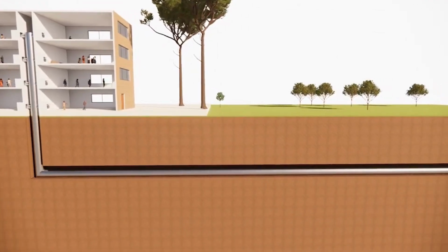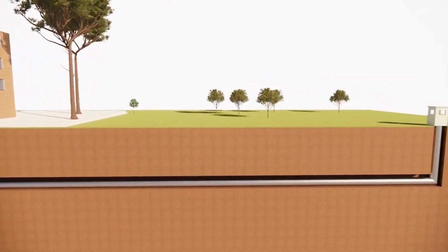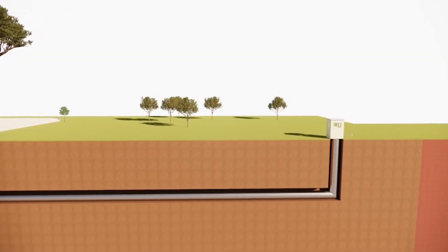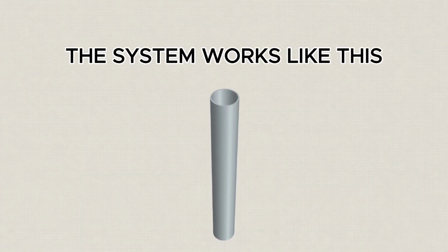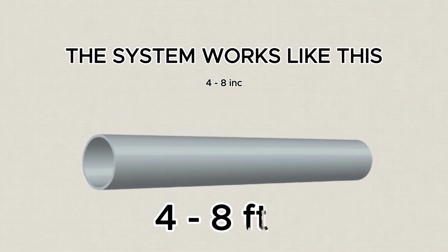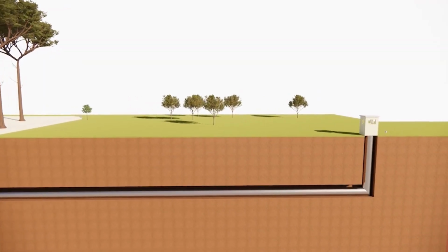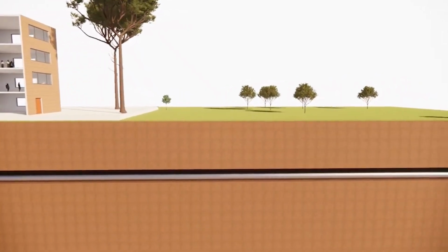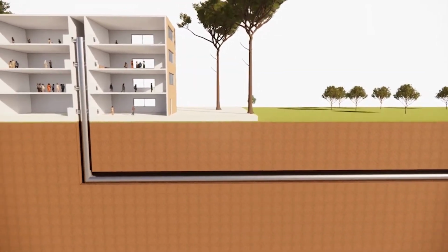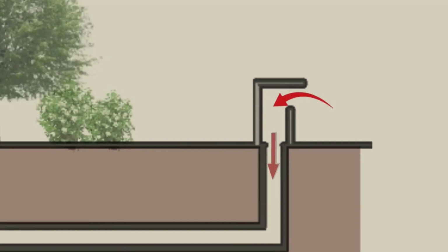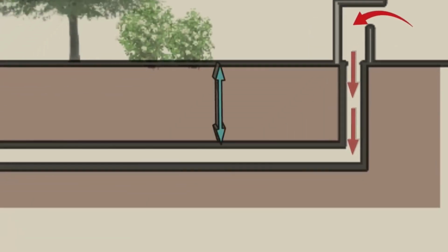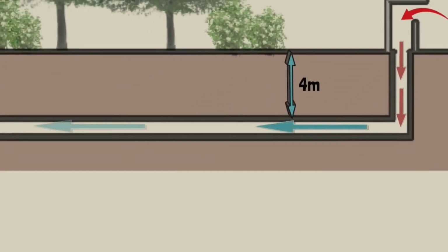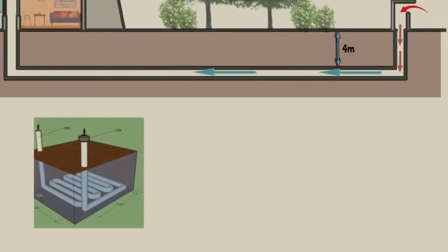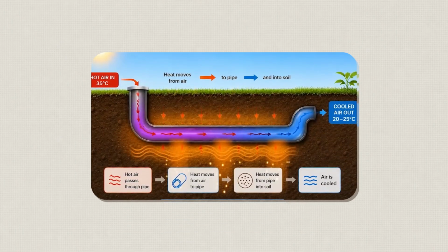An earth tube, also called an earth air heat exchanger, or EAHE, exploits that difference directly. The system works like this. A pipe, typically 4 to 8 inches in diameter, is buried at a depth of between 4 and 8 feet and run horizontally for a distance of between 50 and 150 feet before entering the building at foundation level. Hot outdoor air is drawn into the inlet at one end. As that air travels through the pipe, it is in constant thermal contact with the surrounding soil. The soil absorbs the heat from the air.